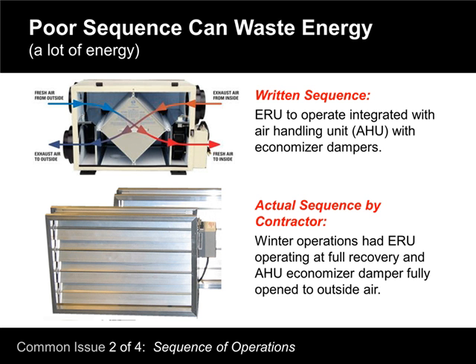And a lot of things we see will be valves that operate simultaneously instead of after each other. I've seen instances where a cooling valve is open and running and the heat after it is trying to reheat the air back up that was cooled down. You'll see dampers that end up open and heating. Cold weather outside, they'll drive the heat on when they don't need to be. There's warm enough return air to blend in. So it's important who's going to run the sequence of operation for the control.